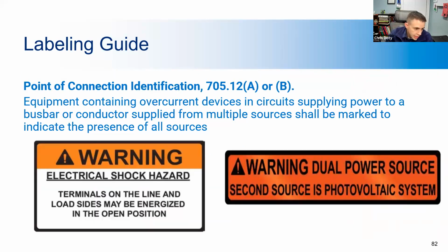Here we have the point of interconnection identification. This requirement is simply to identify all sources of power supplied to a bus bar or conductor, which tells that even if you shut down one of the disconnects, it could still be energized, and it tells that there's multiple power sources.